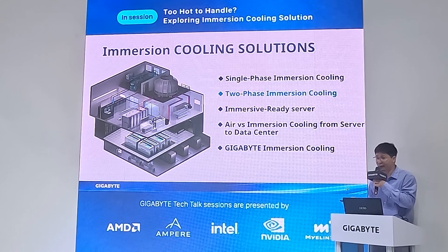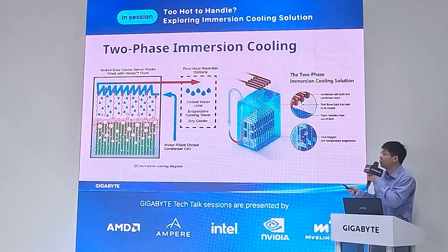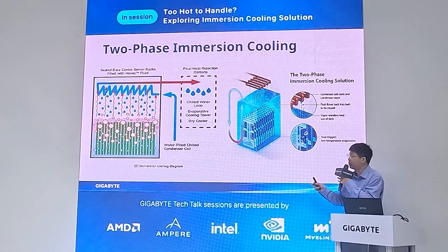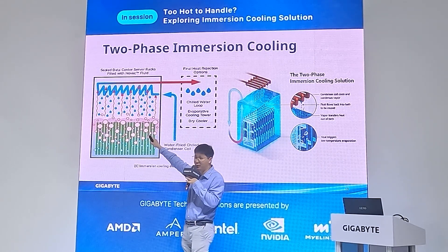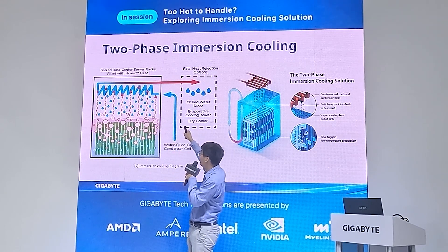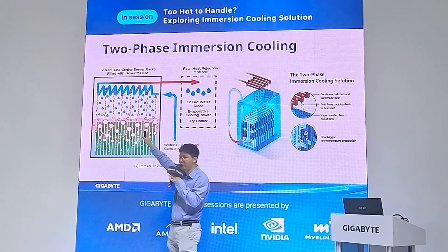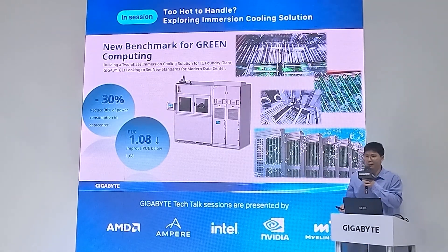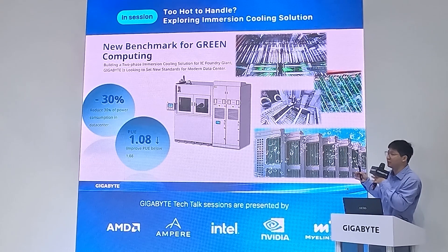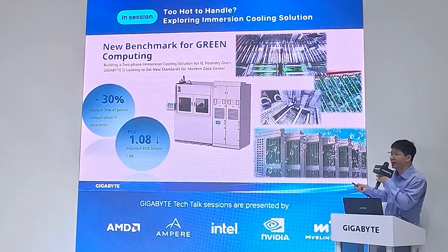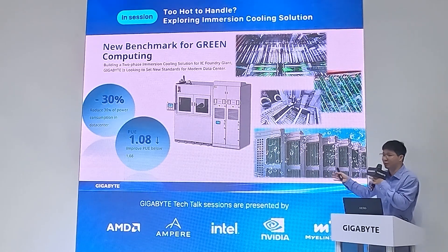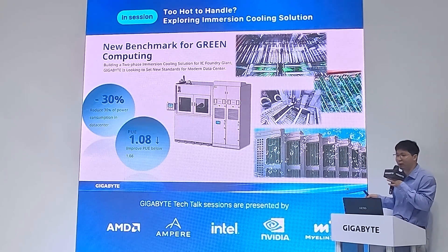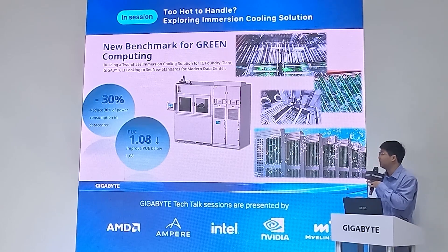Now for two-phase immersion cooling. We call it two-phase because when the liquid reaches its boiling point, it transfers from liquid to vapor. After temperatures drop via the cooling tower, the vapor transfers back to liquid and returns to the tank. GIGABYTE has a very successful case with an IC foundry giant, where power consumption was reduced by 30% and PUE lowered to 1.08, assisting the customer toward carbon zero emission by 2050.